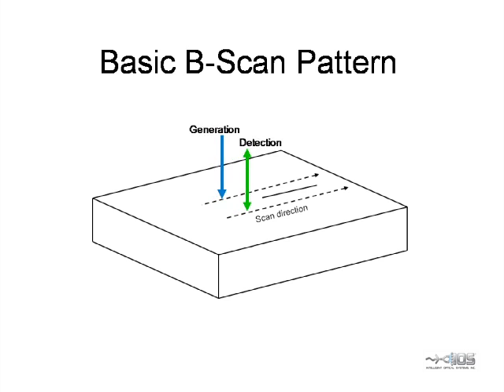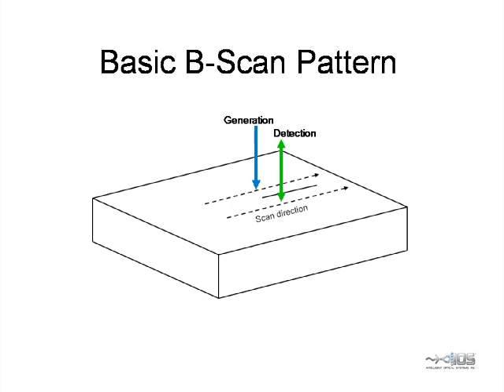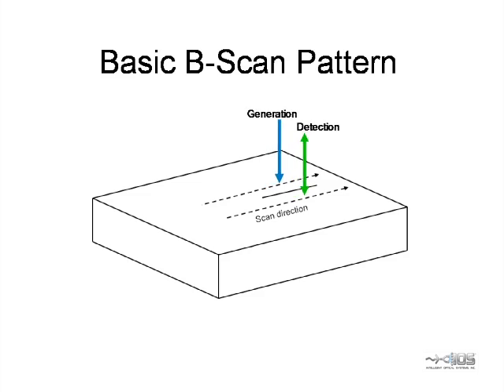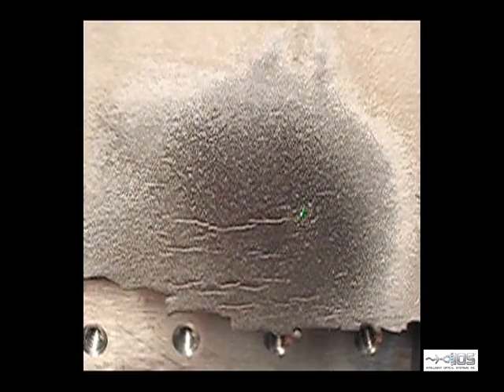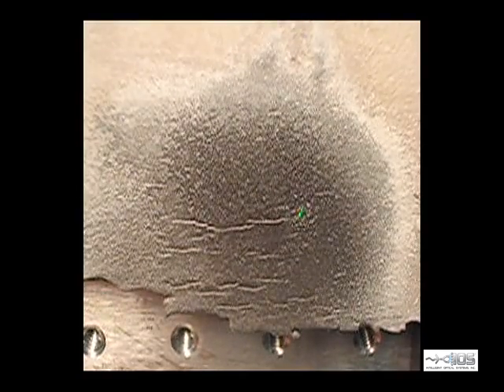For scanning, both beams are moved parallel to an individual crack. In this video, we show both beams being scanned along a single crack. The beam spacing is 4 millimeters. The generation spot looks large only because it is overexposed.